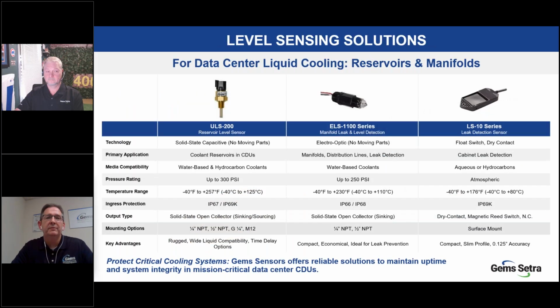Next, we're going to move into the level products. So we have on the left and center two non-moving part solid state products, and on the far right an actual moving part, but it doesn't really move that much. Moving down through the ULS 200, this is a capacitive style sensor. It is ideal, as Dennis mentioned, for the aqueous coolant used in the CDUs. It has a high pressure rating and a very high temperature rating. The ingress protection is very solid. It utilizes an open collector style, so it's sinking or sourcing based on the selection that you make, with a wide range of mounting options. It's very rugged. It has high compatibility with various liquids, and we actually have the ability to program time delays, unlike some of the older products, where now with the electronics today, we're able to build that right in. So if there's any sloshing or changing, it could actually dampen that out with a time delay.